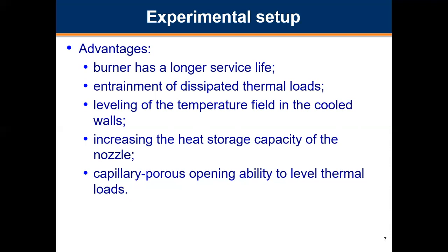Thus, the temperature field in the heat-stressed elements of the burner is leveled and the appearance of sharply varying destructive loads is excluded. The listed advantages are realized both at nominal load and at alternating and emergency operation modes. No blockage of the cooling cavity by steam bubbles. Coolant consumption is drastically reduced by a factor of 4, which saves water.